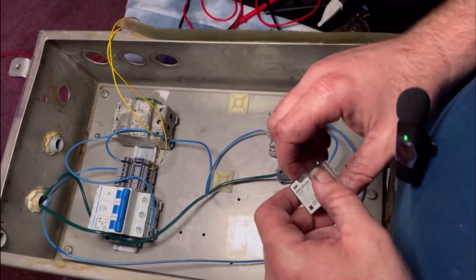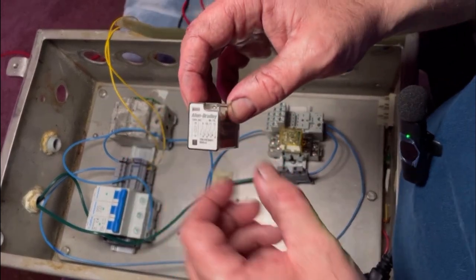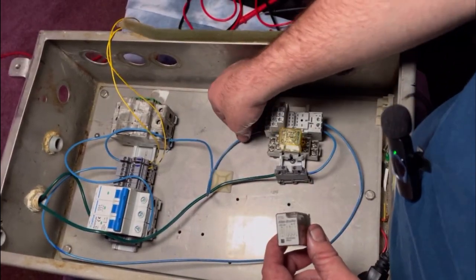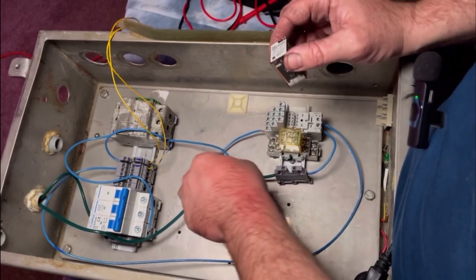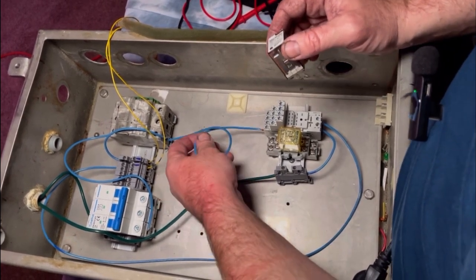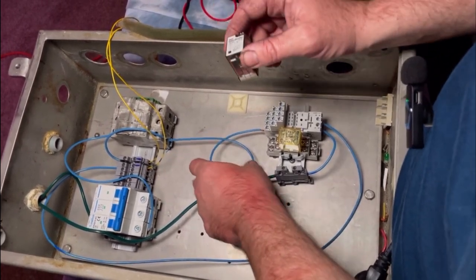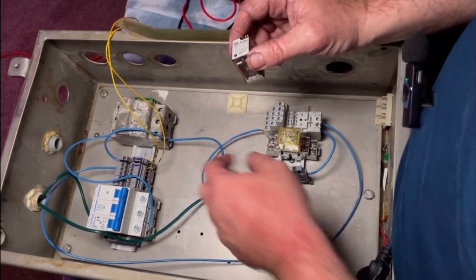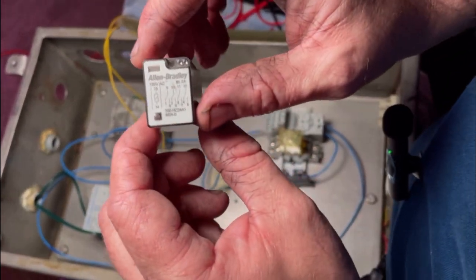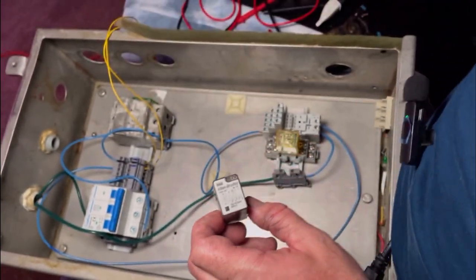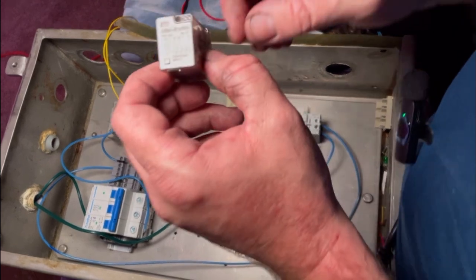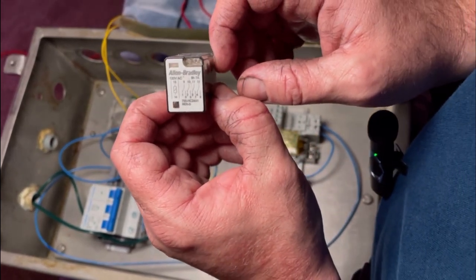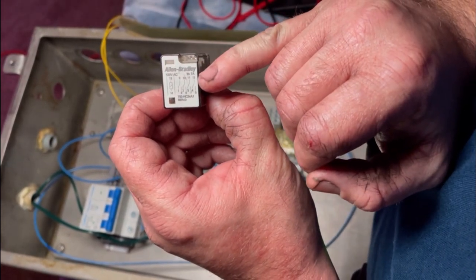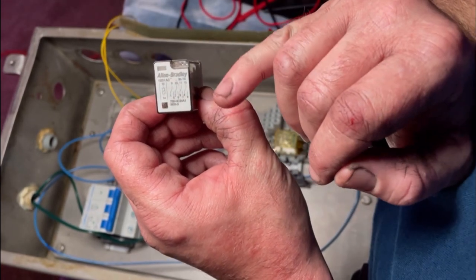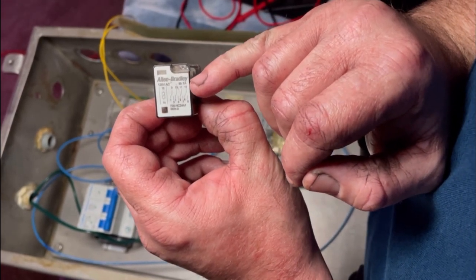All right, so I got my 120 volts for the common side of my contact on my relay. In other words, this is the power that's going to be feeding my pump through the relay contact. I pulled it off the bottom side of the fuse, just as we used in the schematics. I terminated it right here. I think that's point 12. Yep, on point 12. Right there. My hands are dirty from my job, by the way. People, don't judge me. Right there on point 12.